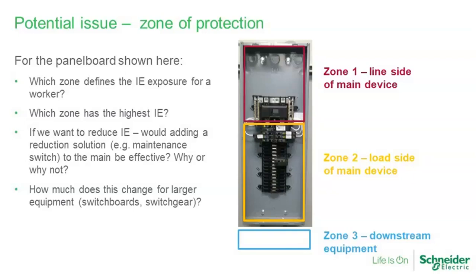They're freestanding on the floor. But one of the things that they would share in common is that there's not a lot of isolation between sections or between compartments in a low voltage switchboard. Low voltage switch gear or medium voltage switch gear, which does have breaker cubicles and isolated compartments, maybe things are different. The point being, this is an example of something that should be considered when we're looking at doing arc flash hazard calculations. Equipment construction is really one of the variables out there that ought to be looked at.